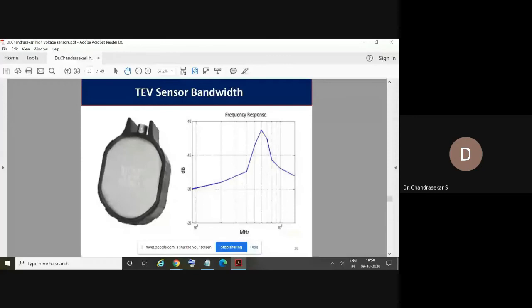So yeah, you might have seen how they are using the TEV sensor technology for measuring PDs. It's a very compact handheld device. So you can simply touch any metallic point or surface, and then you can easily measure the PD occurring inside the equipment, be it a transformer or any other equipment. You can monitor PD in switchgears or panels through these handheld devices. Such a level of technological development is happening in sensor technology.